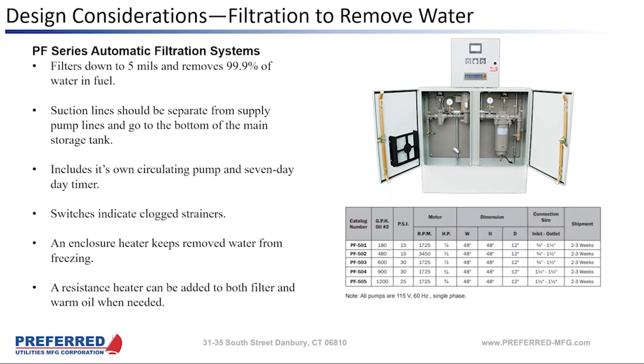I saw a design that had one of these Racor filters between the supply pumps and the day tanks, and then it had a bypass. And I guess the bypass was there in case the strainer ever got clogged. But if the strainer got clogged, the last thing you want to do is bypass that strainer, because then you're sending dirty oil directly to your day tank and then to your engine. Right. Now, the engine will have its own canister filter in it. So this isn't your last line of defense, but the canister filters inside the generator enclosure are usually pretty small, and if you have really bad fuel, they're going to gunk up pretty quickly. Yeah, once those plug up, then you're in real trouble.